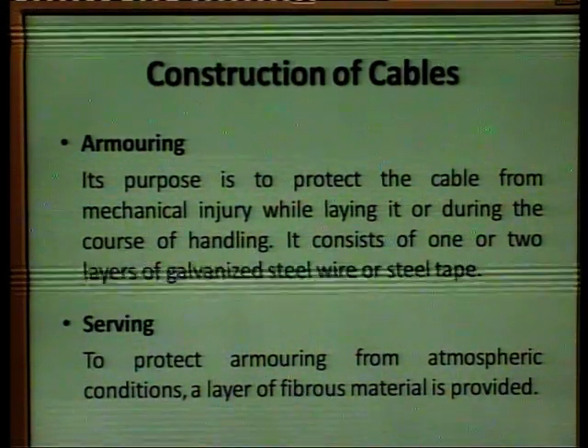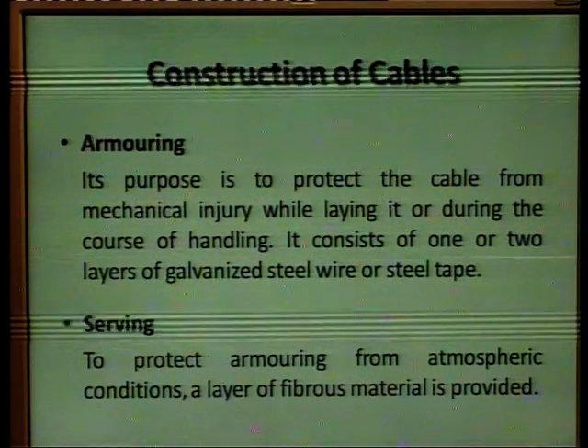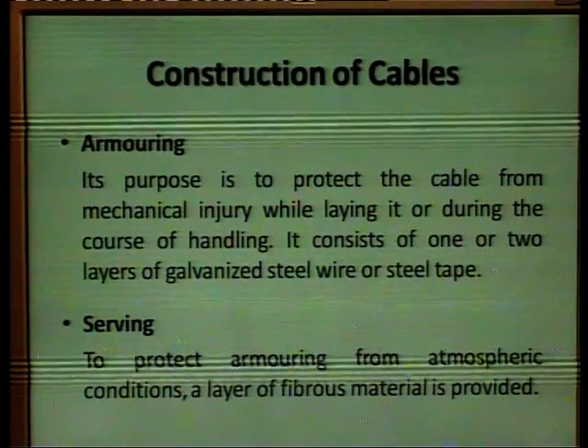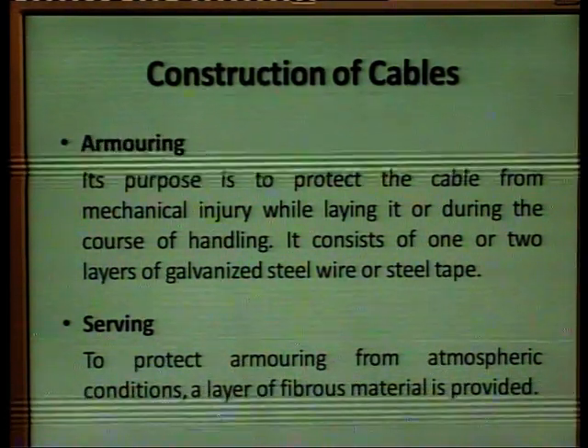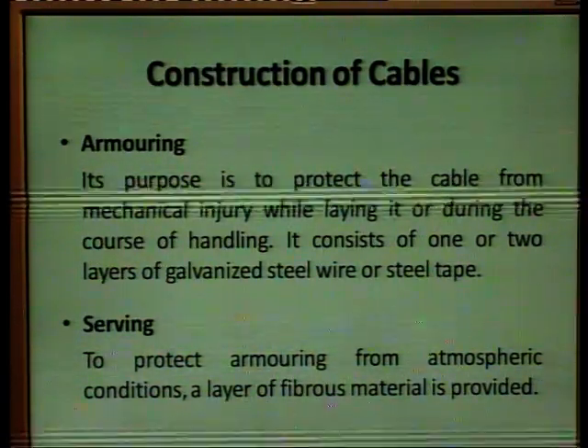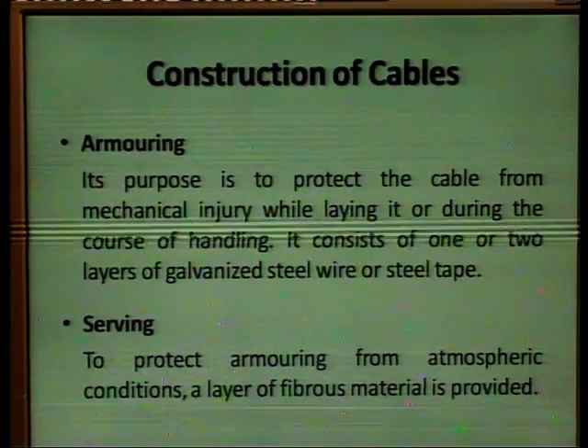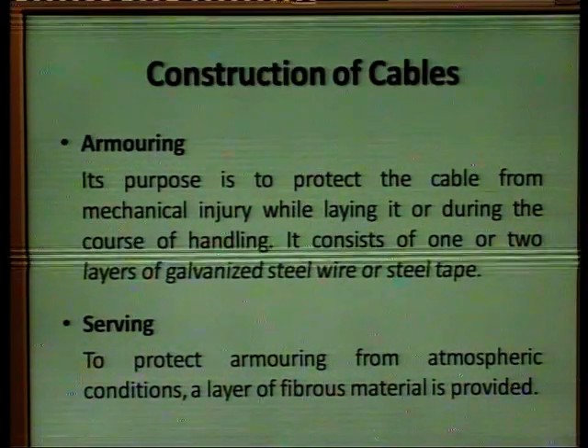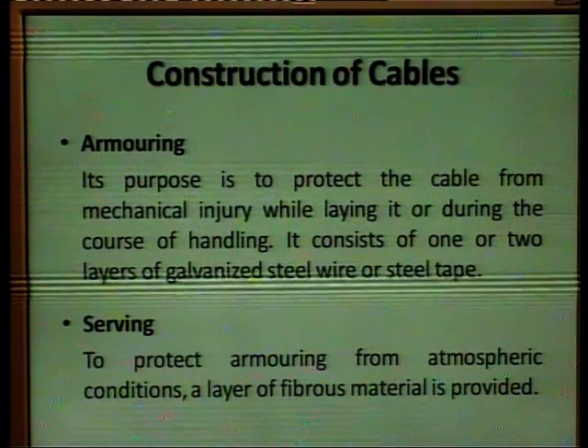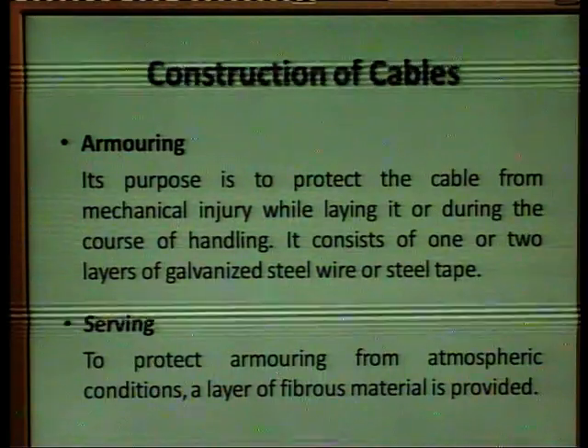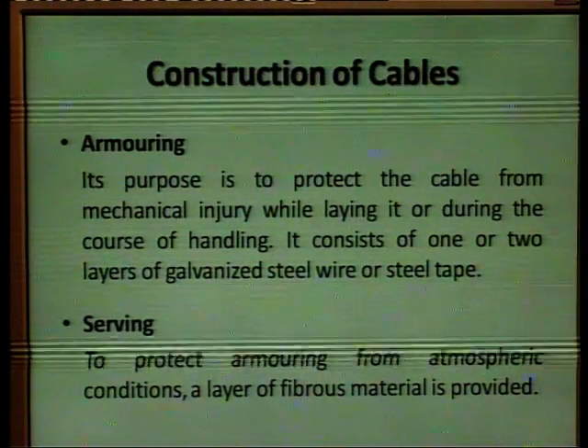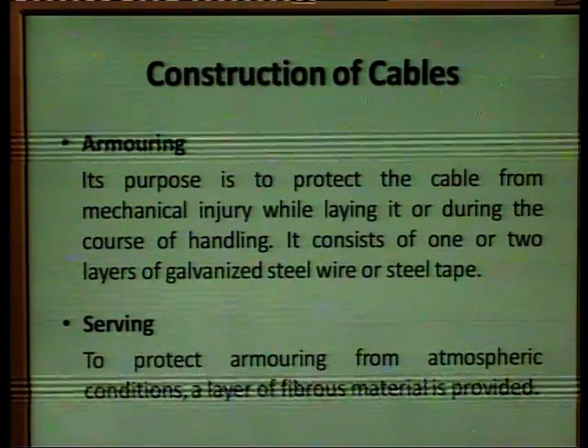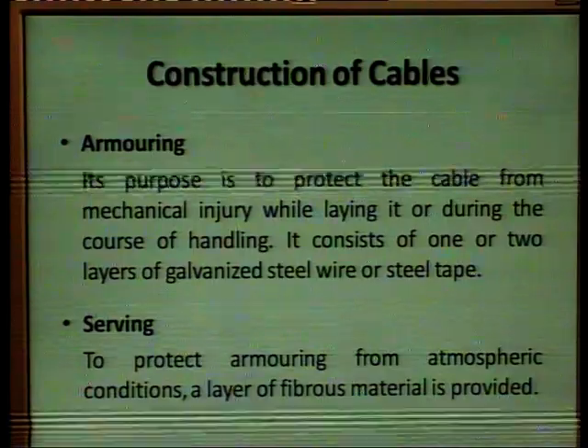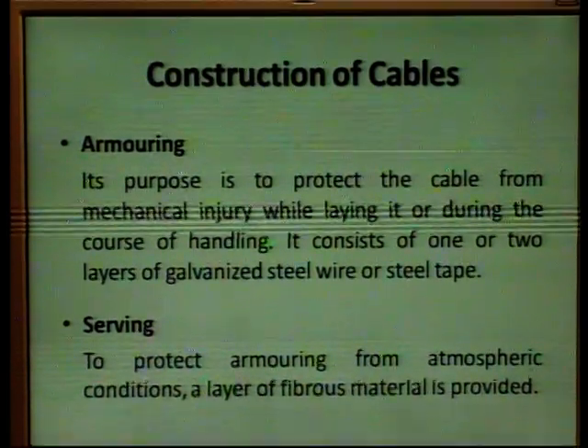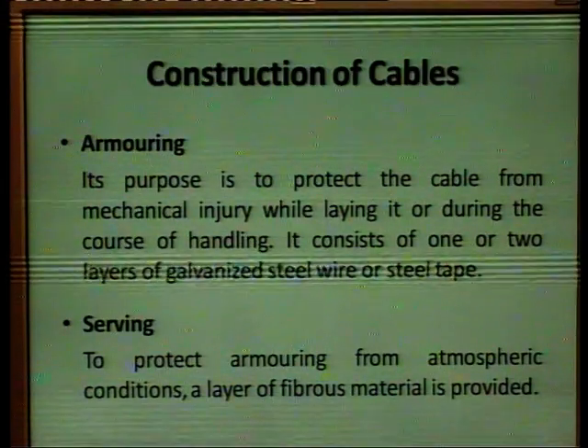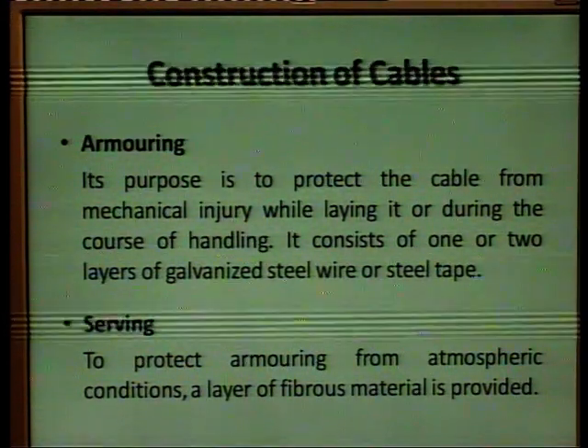And then we have the armoring. Its purpose is to protect the cable from mechanical injuries while laying it or during the course of handling. It consists of one or two layers of galvanized steel wire or steel tape. Then in the last we have the serving. To protect the armoring from atmospheric conditions, a layer of fibrous material is provided, which is known as serving. It is the outermost part of the cable.